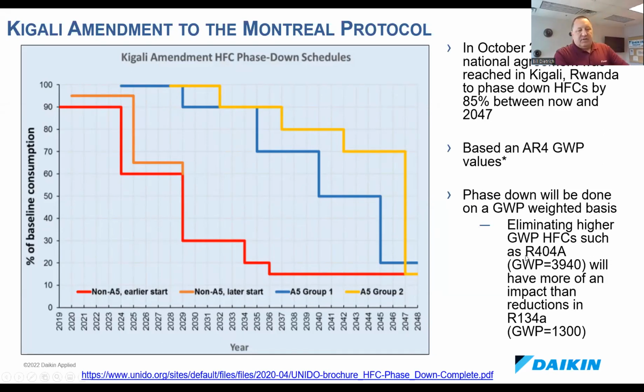A simple example: if you take a refrigerant like 404A, used in a lot of supermarket refrigeration, that has a GWP of 3940, whereas 134A has a GWP of about 1300. So if a manufacturer had an allowance of 4,000, they could make 1 pound of 404A, or 3 pounds of 134A — both meet the 4,000 cap. So it's up to the producers to decide which is more economically advantageous to make. But in general, a GWP weighted system like this tends to drive the higher GWP fluids out of the market faster.